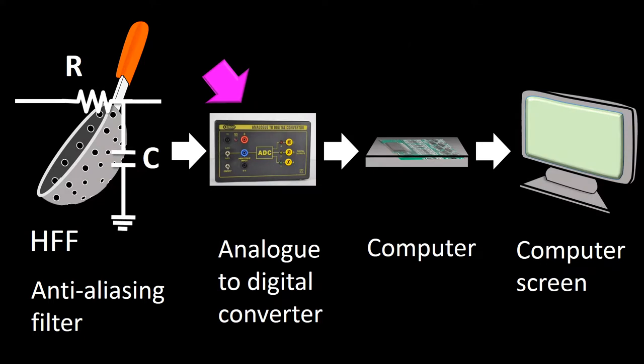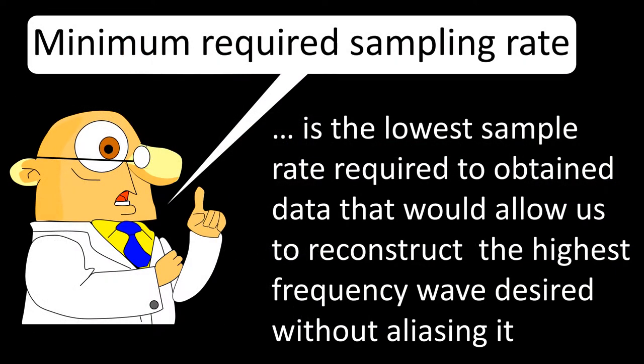The sampling rate is a function of the analog-to-digital converter. The minimum required sampling rate consists of the lowest sampling rate required to gather enough data to reconstruct the highest frequency present in a wave without aliasing it. From the clinical point of view, it is the lowest sampling rate required to accurately reconstruct the highest frequency wave that we desire to see.